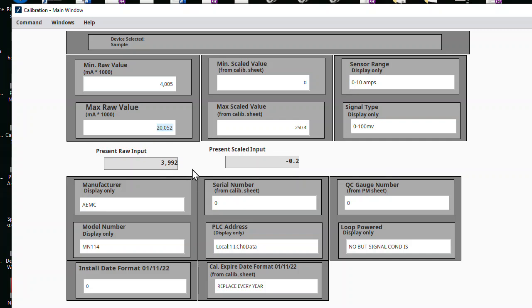That's going to tare it to zero and send the low signal. We don't really care what the meter says; we only care what zero means. Whatever zero sent to the PLC, we're going to call zero. Right now we are sending a 3.992 milliamps signal. So that now becomes our low signal. I don't really care about the calibration sheet because this is zero; we're taring to zero. That's always going to be a little different.